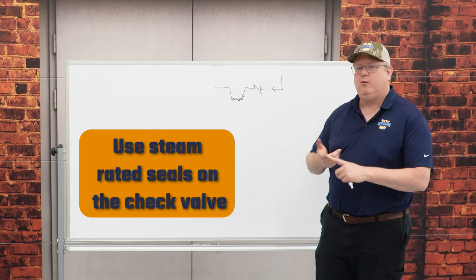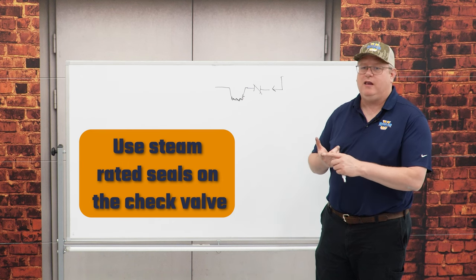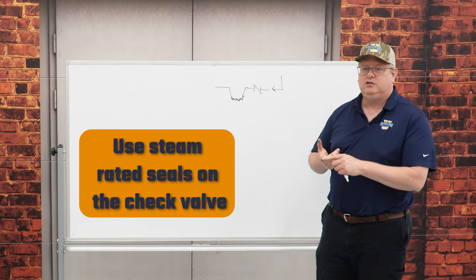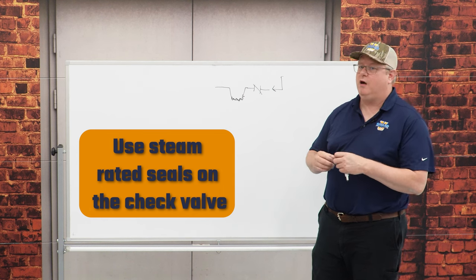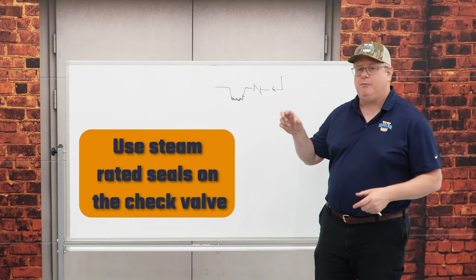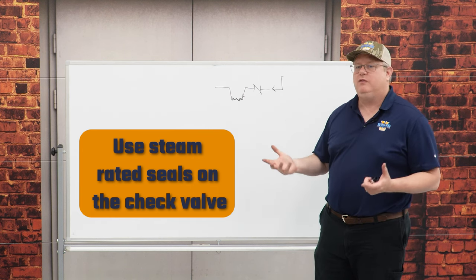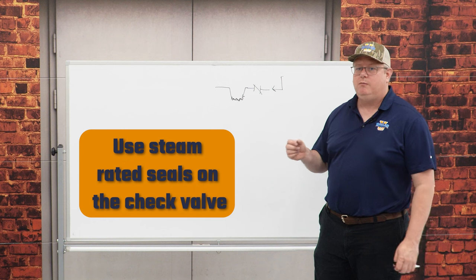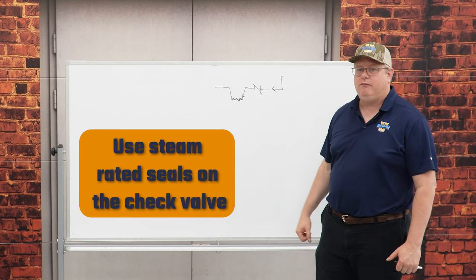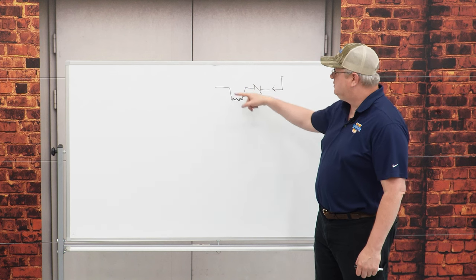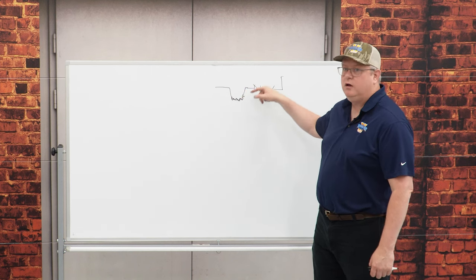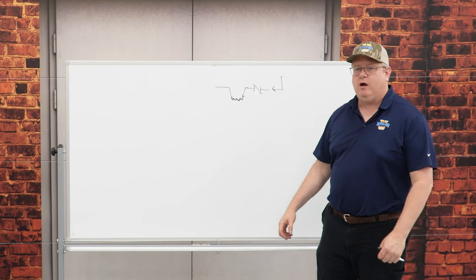In addition to that, we probably want to look and make sure that we've got steam-rated seals on that check valve. If we've got an o-ring style or something that's got black rubber in there, it's not going to hold up very well. But a good Teflon-seated valve should last for a good number of years, and adding just a little siphon loop before it will actually protect that valve as well.